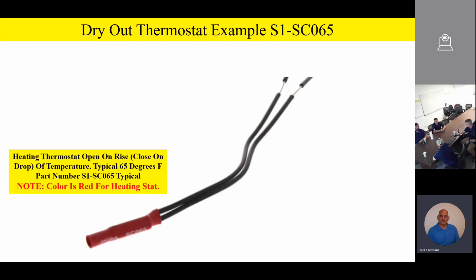So as we take a look at it, this is what that little construction thermostat looks like. You guys have seen these before, the sheet rockers and all, they'll use these to run the heating equipment to dry the house out when they're doing their sheet rock. So again, this is a heating thermostat. It opens on rise of temperature, and you're going to select one that's 65 degrees. And again, the Source One part number is an S1-SC065, which is typical. And remember, the color red is for the heating stat.